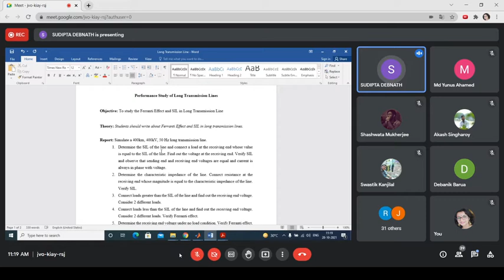Do you remember this equation, SIL equal to line voltage square by Z0 or ZC? Do you remember that surge impedance loading is VL square by ZC? If you don't remember, go through the class notes of your 5th semester. This is the SIL. If this voltage is in kV, you will get the result in megawatts, because of 10 cube whole square. If you write it in volts, you will get the result in watts.